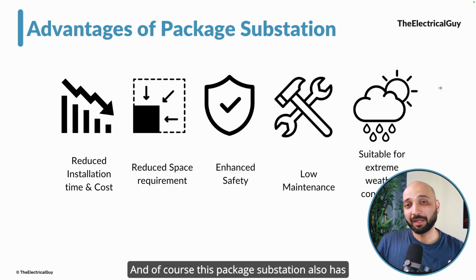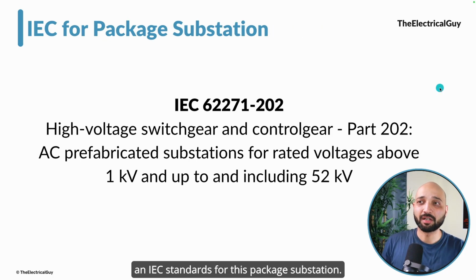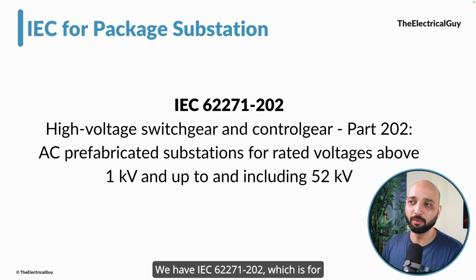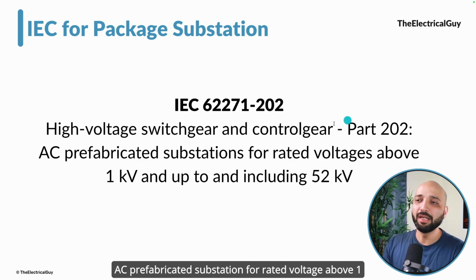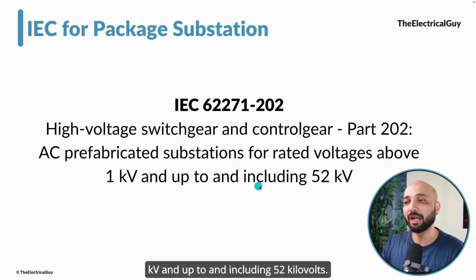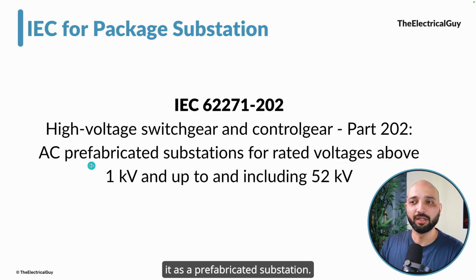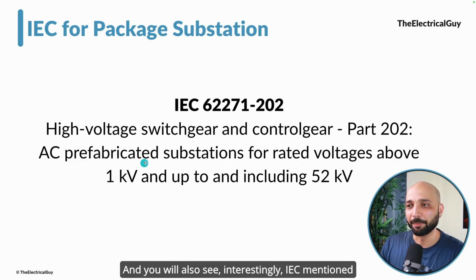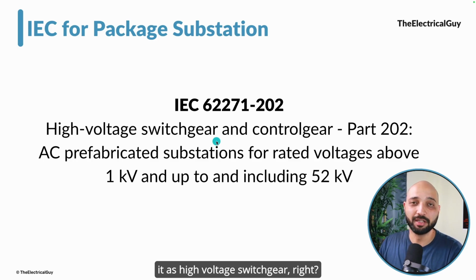And of course, this package substation also has IEC standards. For this package substation, we have IEC 62271-202, which is for AC prefabricated substations for rated voltage above 1 kV and up to and including 52 kilovolts. Now you will see IEC clearly referring to it as a prefabricated substation - that's the name used by IEC. And you will also see, interestingly, IEC mentions it as high voltage switchgear.